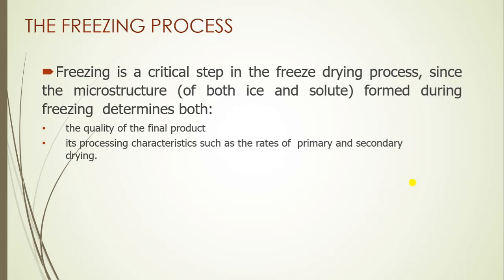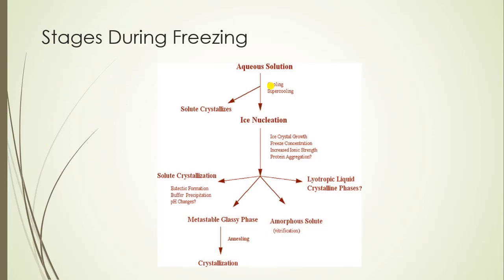Freezing is an important parameter because it determines the quality of the final product and its processing characteristics, such as the rate of primary and secondary drying. Starting with the stages during the freezing process: if we consider an aqueous solution and apply cooling, there is supercooling of the solution. Water does not freeze at 0°C but undergoes supercooling — meaning water remains liquid well below the melting point of ice.